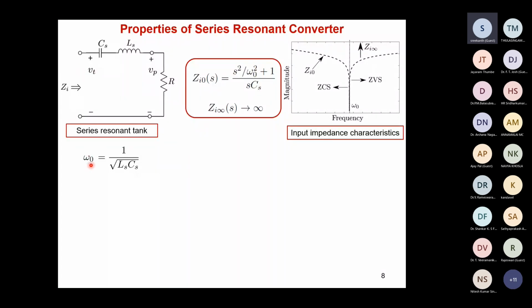So from this itself, we can easily understand that if we switch the full bridge network at a frequency higher than the resonant frequency, we are going to achieve zero voltage switching. And if we switch it at a lower frequency than the resonant frequency, we will get zero current switching. So this is basically the short circuit impedance characteristic.